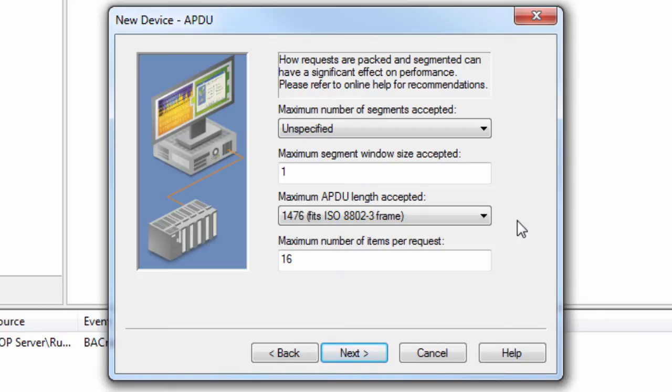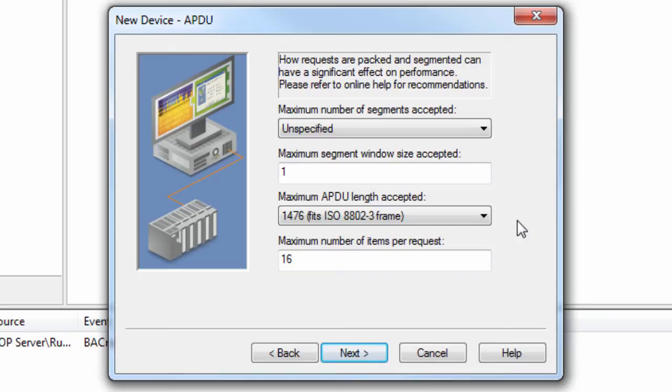Unfortunately, there are no general rules for determining the optimum setting. To refine a particular application, users should experiment with this setting. Devices that do not support read property multiple or write property multiple services should be set to one. Click Next to set the command priority.